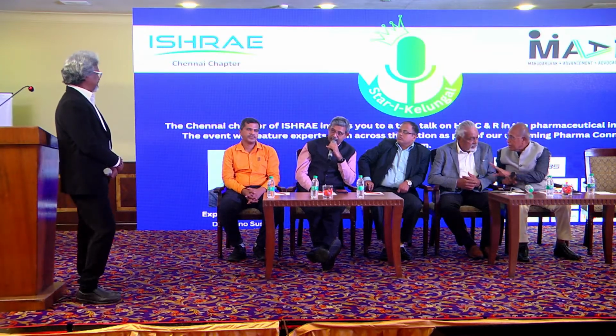Number two, even in the worst case, if dust from the atmosphere gets settled on a conventional duct, there is absolutely no way you can clean it. You cannot go and clean a conventional duct unless you use a robotic duct. And with the insulation over the surface, there is a huge potential for shedding. Those insulation particles, however well we clad them, there's a high probability that they will shed. But a fabric duct does not have any sort of insulation, so it does not shed, number one.